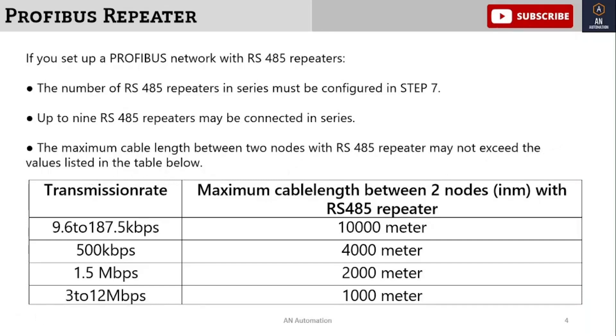The maximum cable length between nodes and the RS485 repeater must not exceed the values in the table. At 9.6 to 187.5 kbps transmission rate, the maximum distance is 10,000 meters. At 500 kbps, it is reduced. At 1.5 Mbps, you need to keep it within 2000 meters. At 3 to 12 Mbps, think about the maximum cable length between 1000 meters.